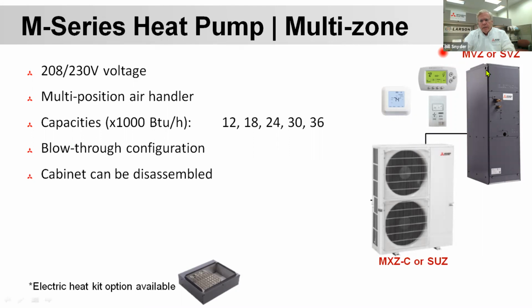This MSZ, MVZ or SVZ air handler. There's 2 models of that. I'll talk to you a little bit. The MVZ is a little taller than the SVZ. They've made it as a design change. The MVZ will be going away. Essentially, it's the same unit, only the SVZ is a little bit shorter. They've taken the electrical panel and moved it from the top down by the blower and chopped about 10 inches off of this for the SVZ.